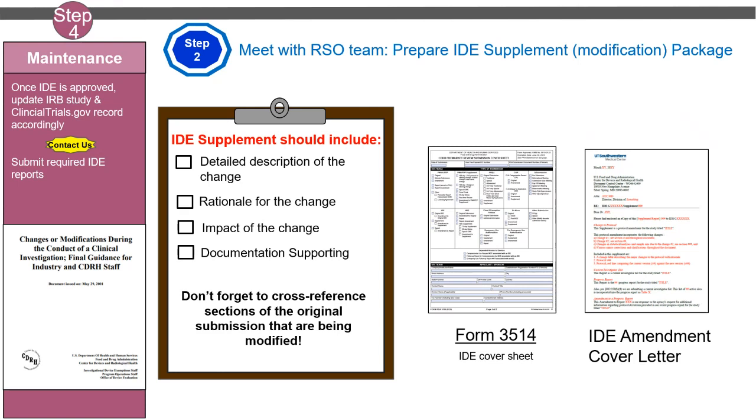When it comes to submissions, amendments subjected to the 30-day review require an IDE supplement package. It is the most elaborate submission item, actually, like a mini IDE application. However, this supplement package is only focused on significant device design or manufacturing changes or protocol changes in terms of the various parameters that we went over.